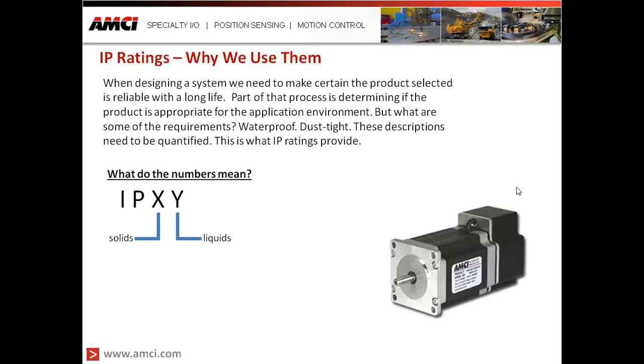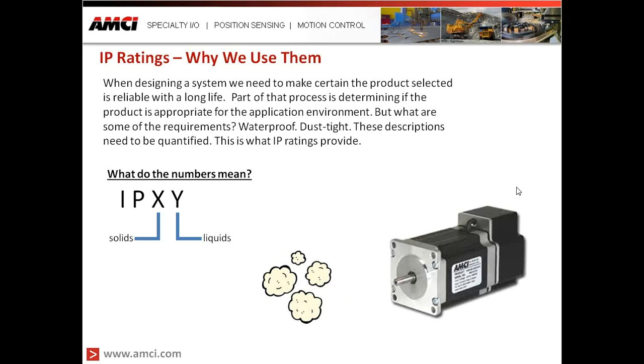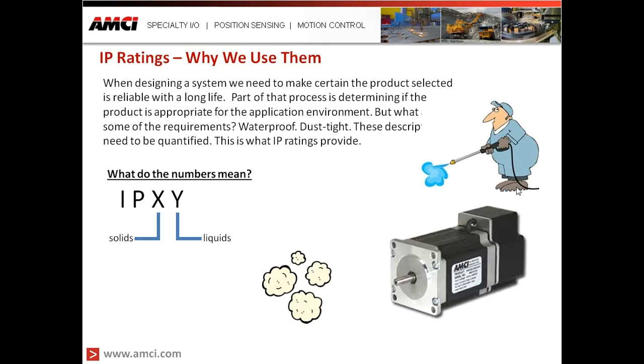What do the numbers mean? What we typically see is IP followed by two numbers, represented here as X and Y. The first number represents the protection level from solids — it tells us whether that enclosure protects from solids as large as a human hand or a finger, or as small as a grain of dust. The second number informs us of the protection level of that enclosure towards liquids, whether that liquid is something as gentle as mist or falling rain, or as extreme as a high-pressure wash.